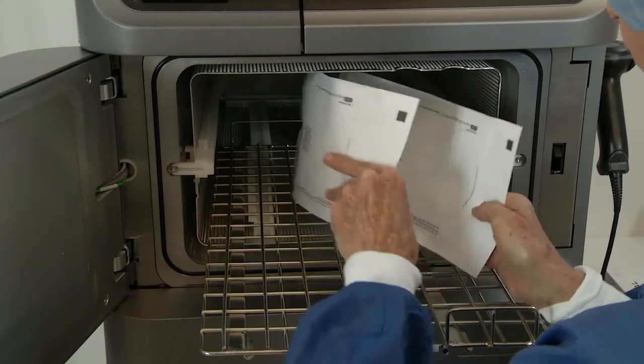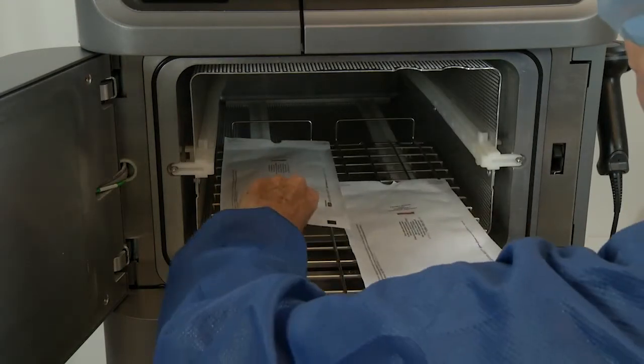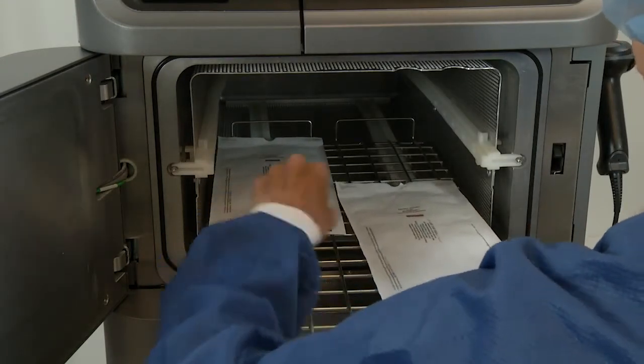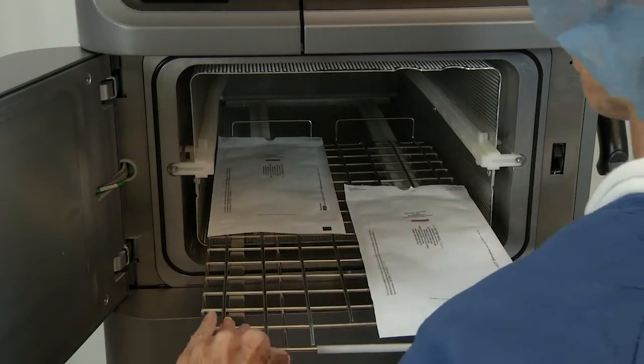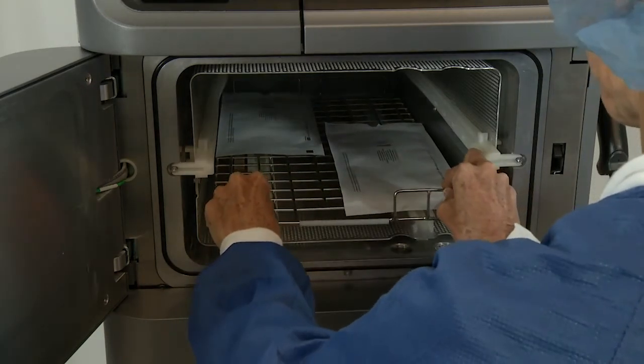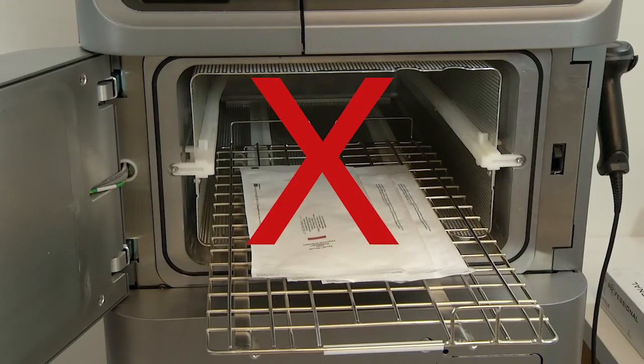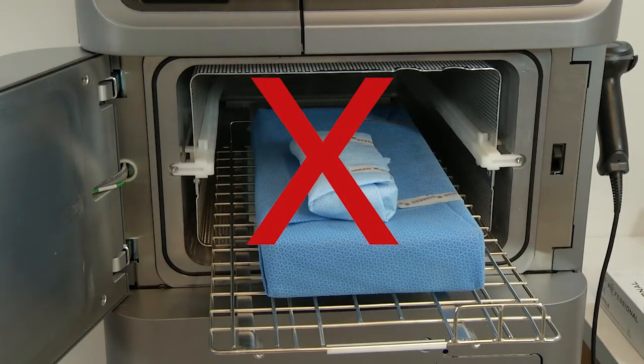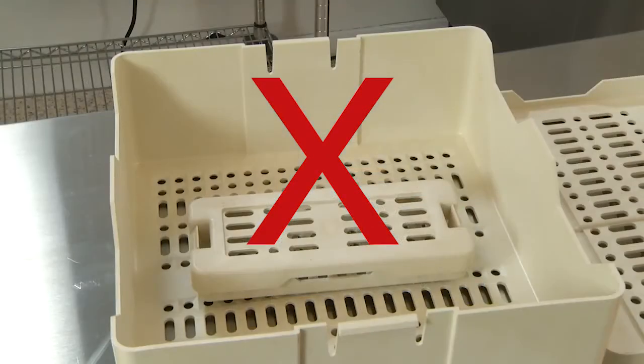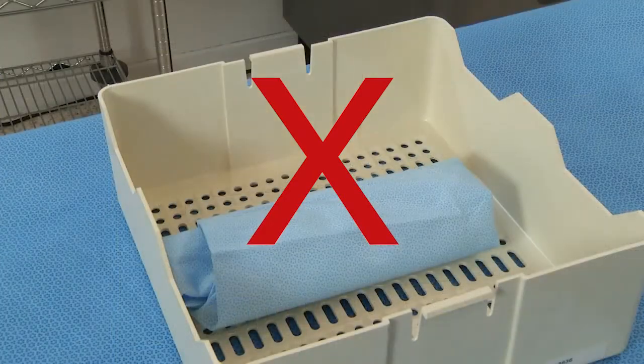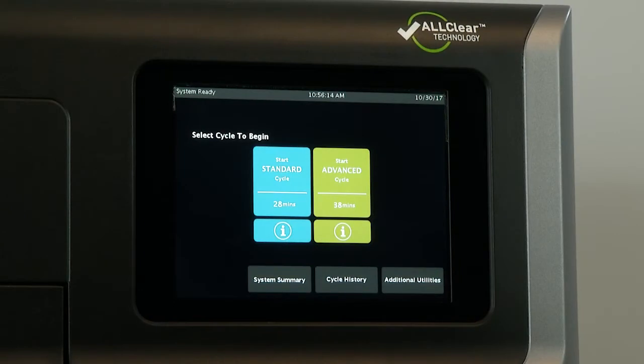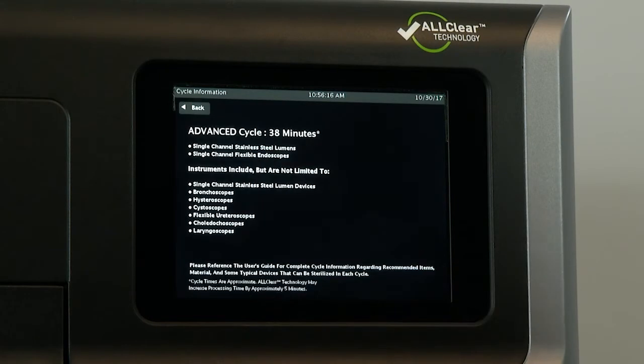Place Tyvek pouches on edge, if possible, and arrange them so that the transparent mylar side of the pouch faces the opaque Tyvek side of the next pouch. Do not stack pouches and do not stack trays in the chamber. Do not place trays within trays or place wrapped instruments within wrapped trays. You can obtain additional cycle information by pressing the information icon at the bottom of the cycle on your STERRAD NX sterilizer with All Clear Ready screen.